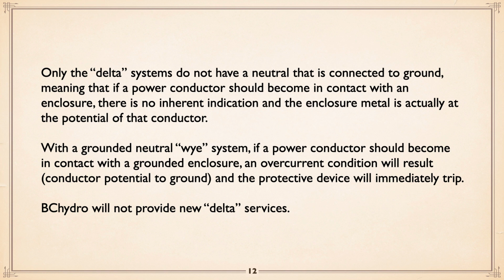In fact, if you knew which one it was, you could actually be leaning against that thing, touch it, fine. All hell breaks loose, of course, when you touch either one of the other two that aren't grounded. And so you have to have systems that indicate that this has occurred to give you warning of it, so that the situation can be corrected, etc., etc. But it is quite possible to walk up and put your hand on it, and you might as well be touching line 1, line 2, or line 3.